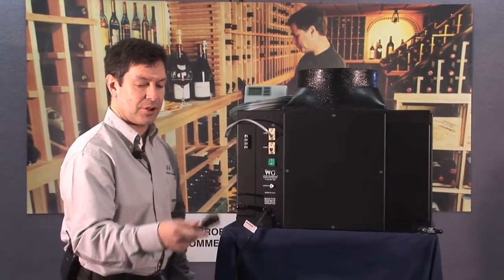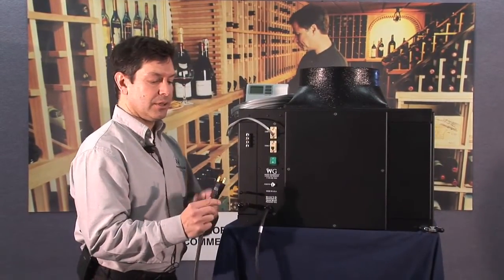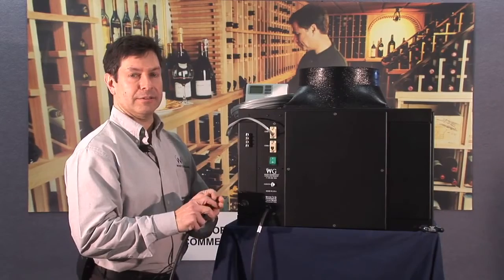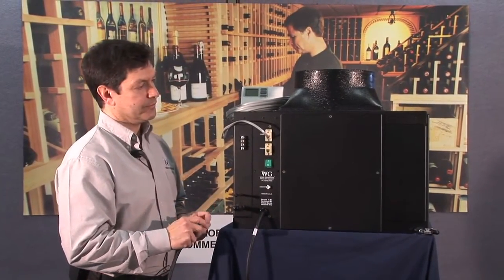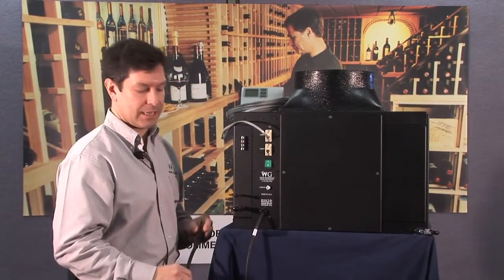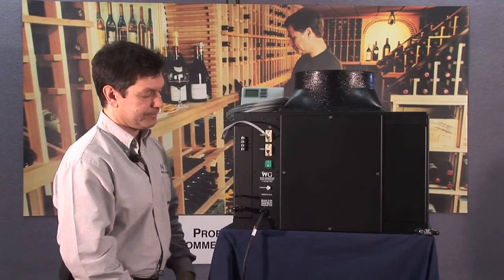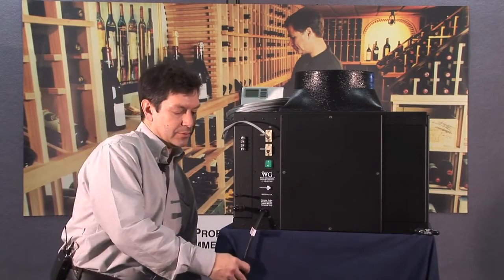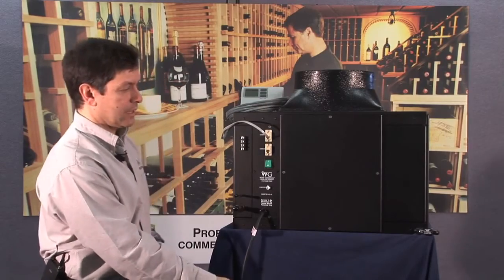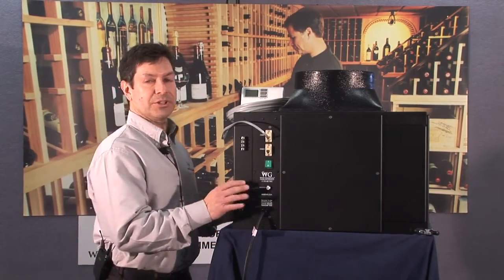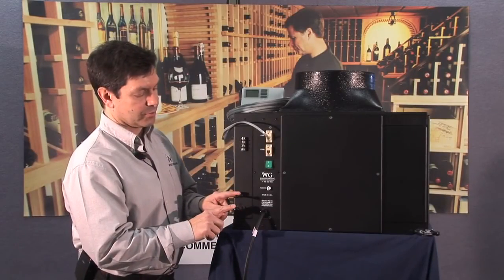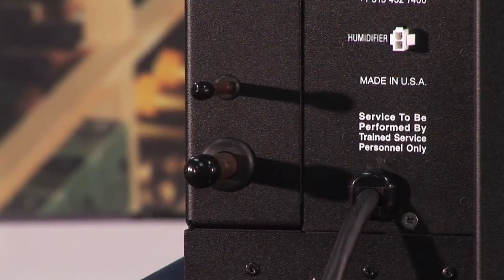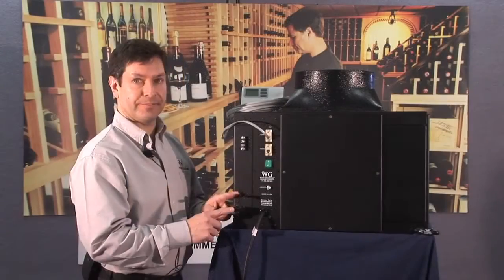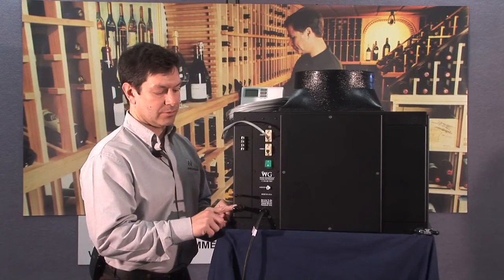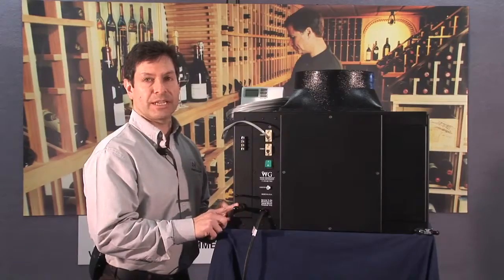This particular unit is 115 volt, which plugs into any standard outlet. We want to point out that that should be a dedicated circuit, so as to not cause any interruptions with power and cause the unit to go down for some reason. See your piping connections centrally located toward the side of the control panel. These will be piped on site to the condensing unit.